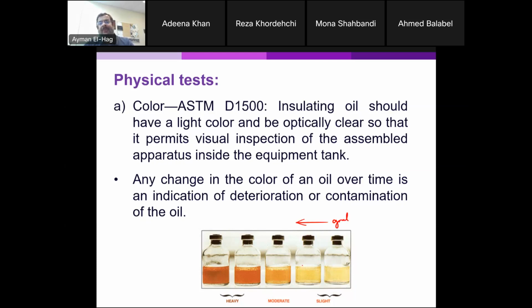And there is a scale for that from 0.5 to 4 with steps of 0.5. So 0.5, 1, 1.5, until you reach 4. 4 is very, very dark. 0.5 is very, very light in color, as if it's a new transformer. So there's a scale in the industry, they have that scale. By specifying the color, you can get a very good idea about the level of the contamination in the transformer oil.